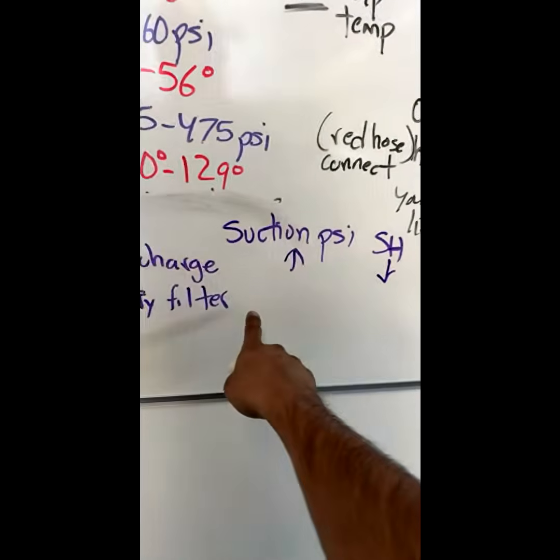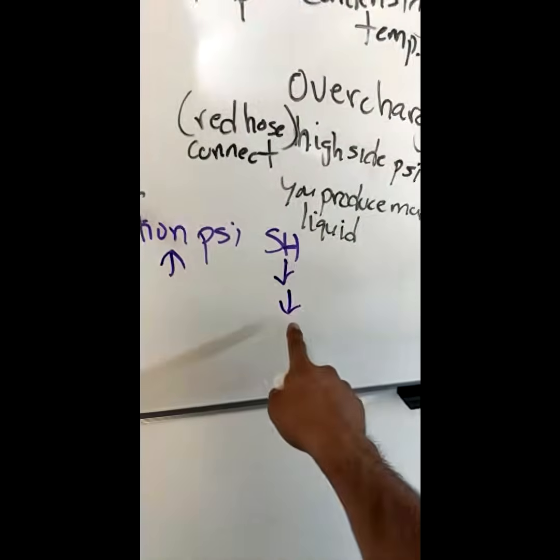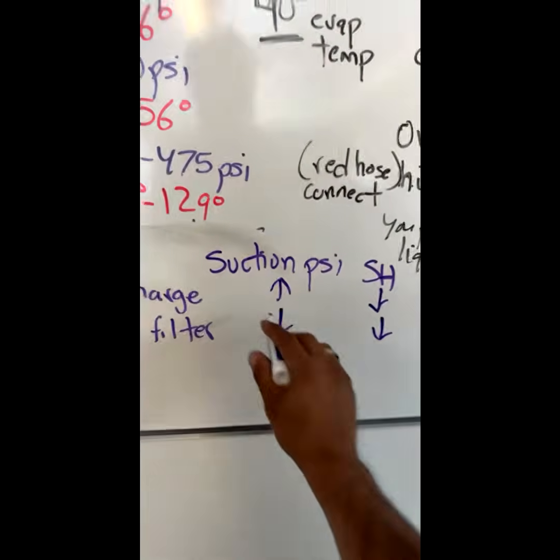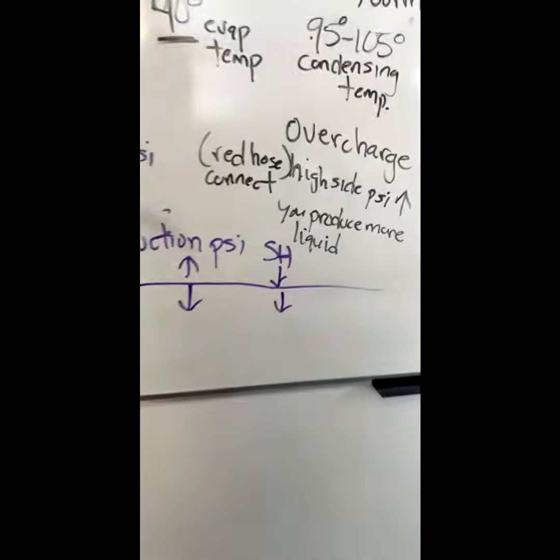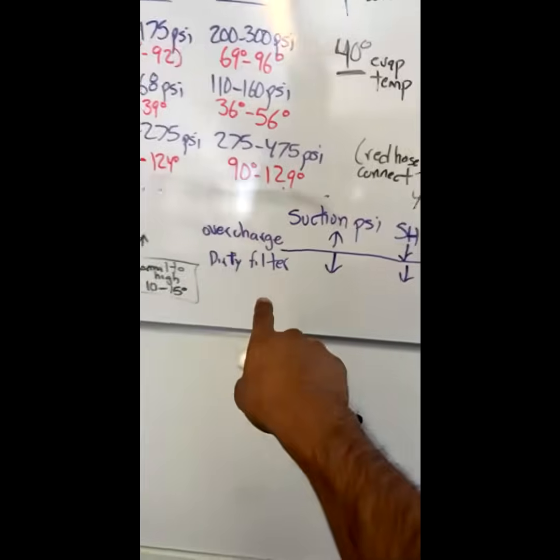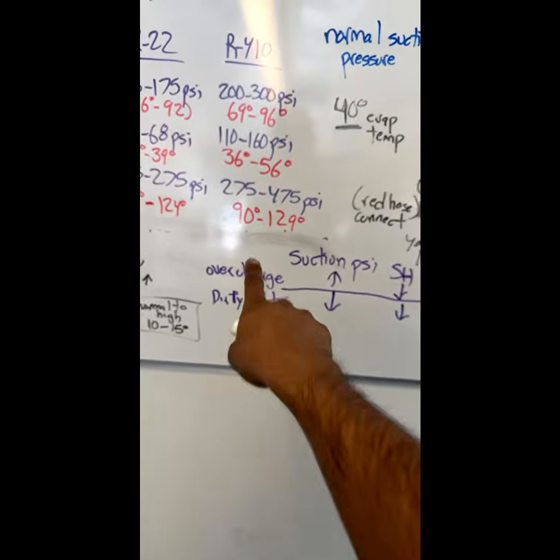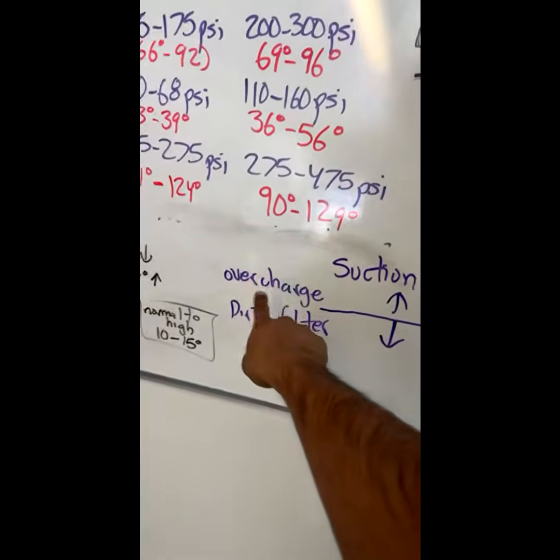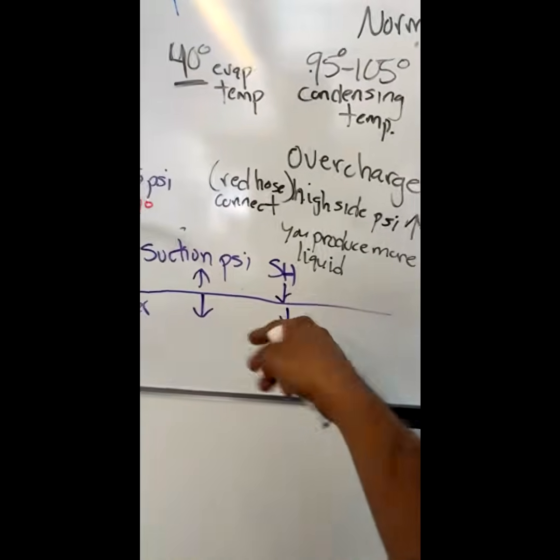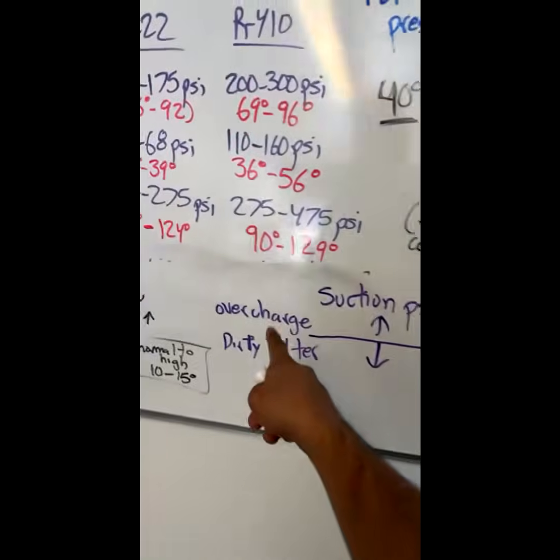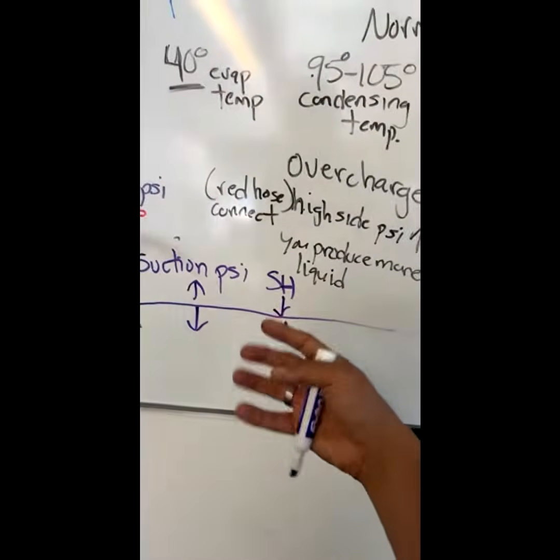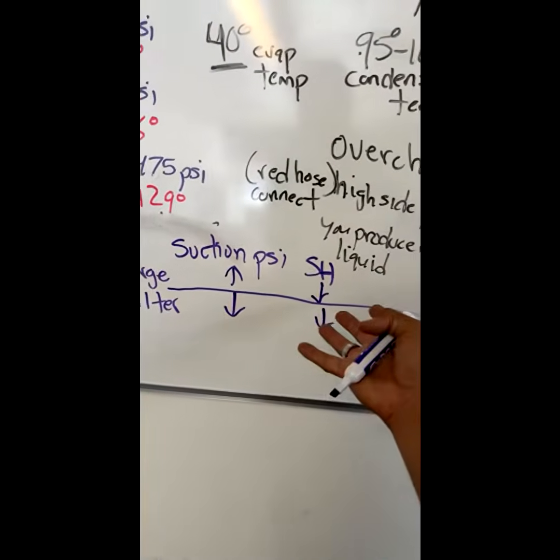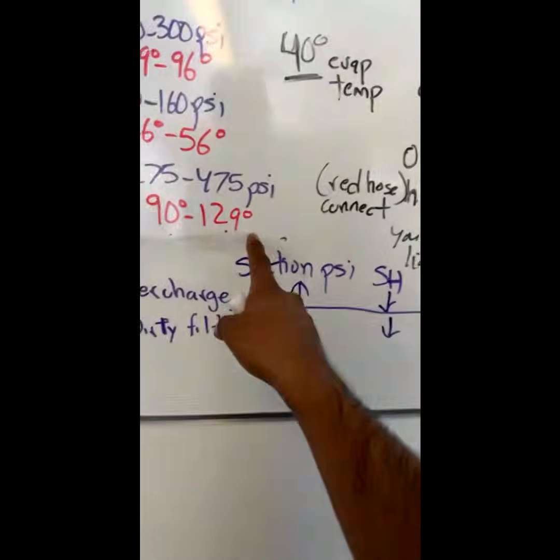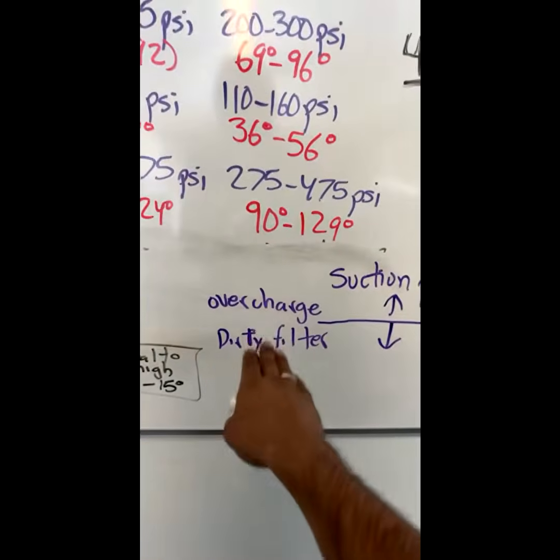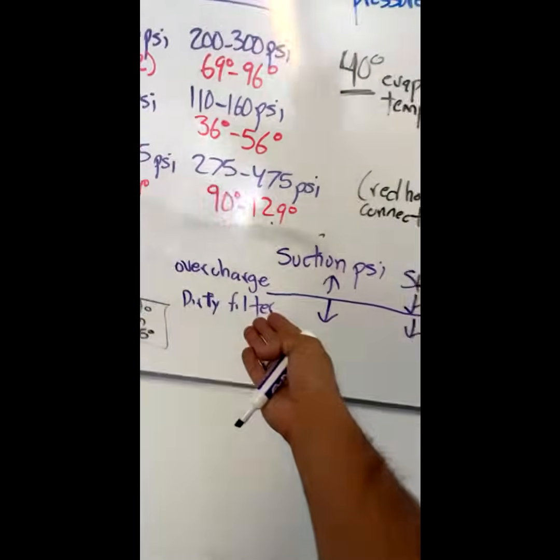With the dirty filter, though, yes, you're gonna run a lower superheat, but your suction pressure is gonna drop, and that's the clear indication as to what's going on with this. Because in both scenarios, with an overcharged system and a dirty filter, you have so much liquid refrigerant going through your evaporator. You're running a low superheat, almost having liquid going into your compressor. With the dirty filter, you're also not boiling off all that refrigerant, so then you remain almost saturated. Superheats are low, but the clear indication to find out the difference between overcharge and a dirty filter or low airflow, and of course you would still be checking subcool.